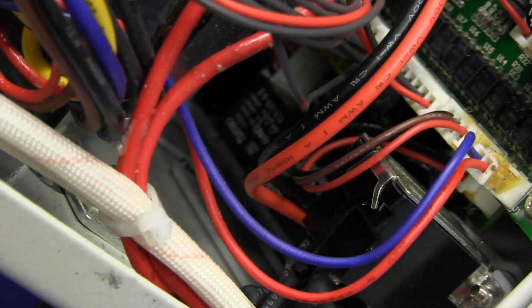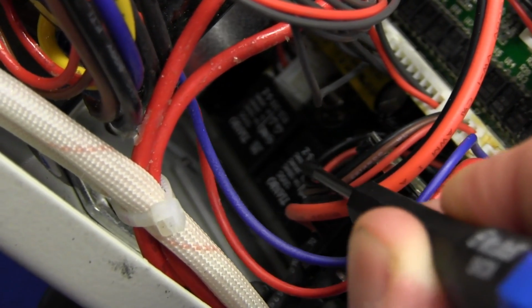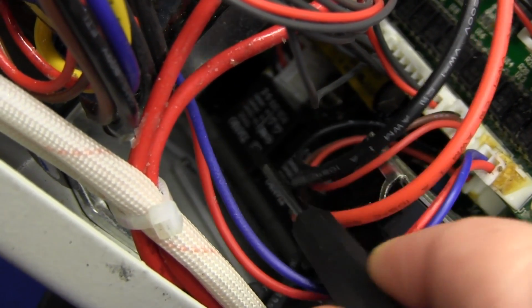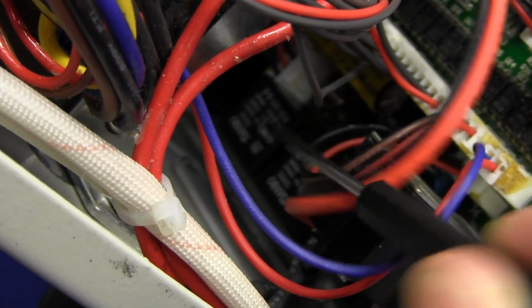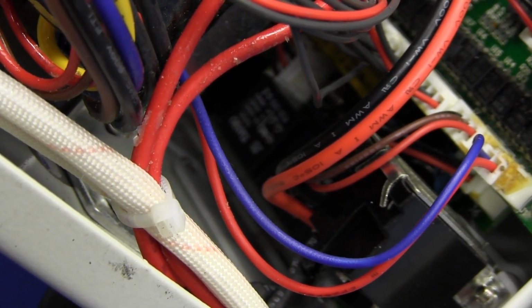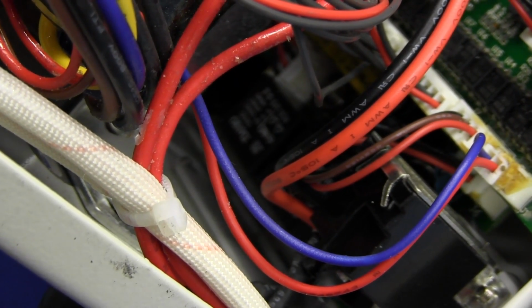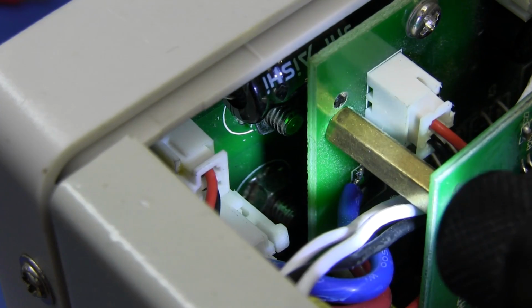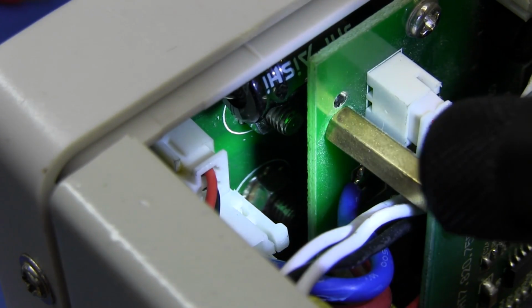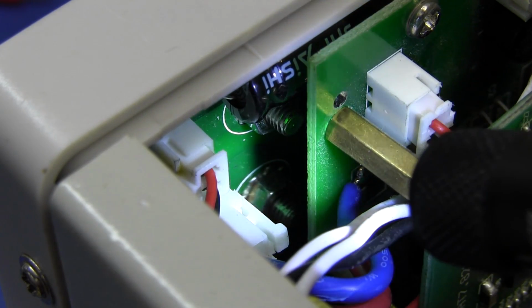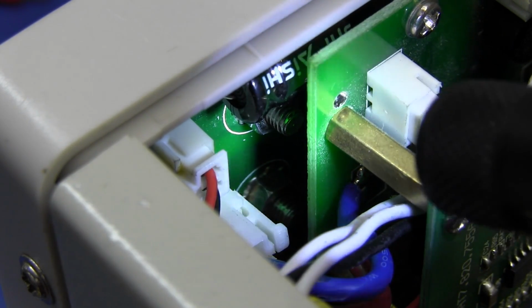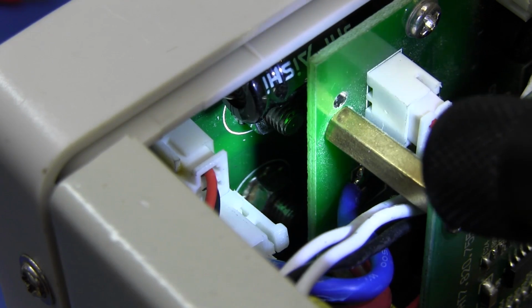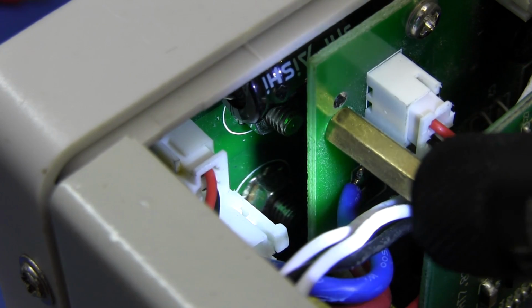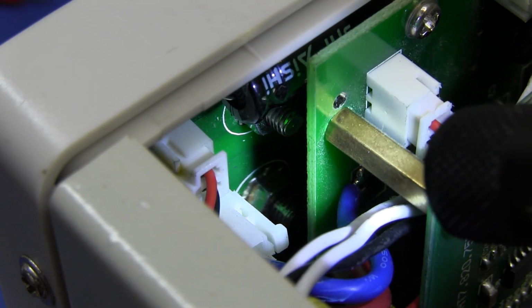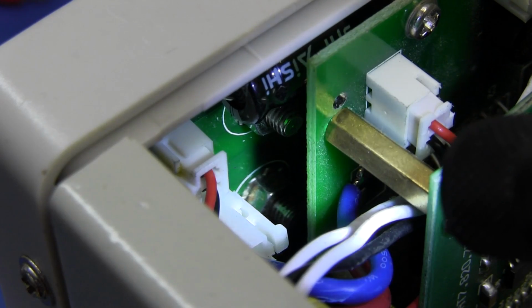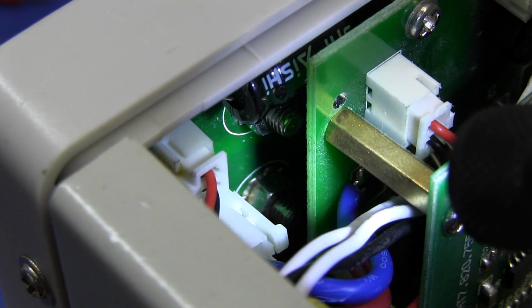Can't quite see them. You might be able to see some relays down in there on the front panel binding post board for your parallel and series mode, for switching your channel 1 and channel 2 terminals either in series, parallel or independent. And you should just be able to see the binding posts down in there attached to the main board. Sorry, very difficult to see. It'd be impossible to take this thing apart. It'd take me hours and I'd never get the bloody thing back together. But anyway, yes, they are shake-proof washers. You can see under the nuts on those binding posts, so they shouldn't give too much of a problem.